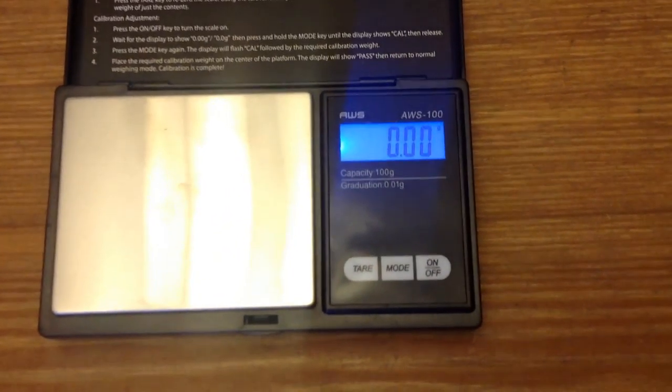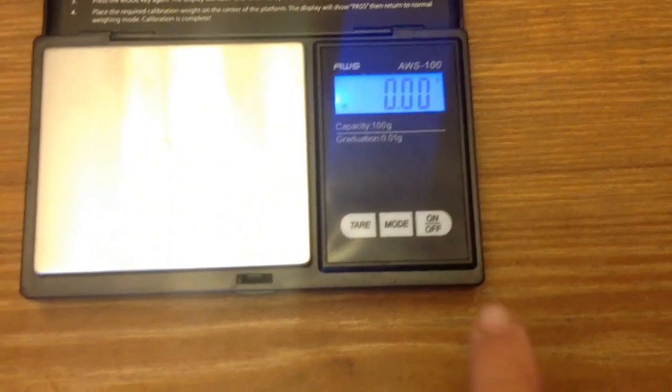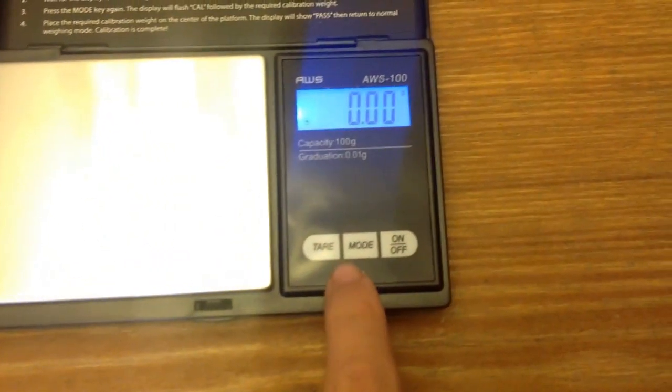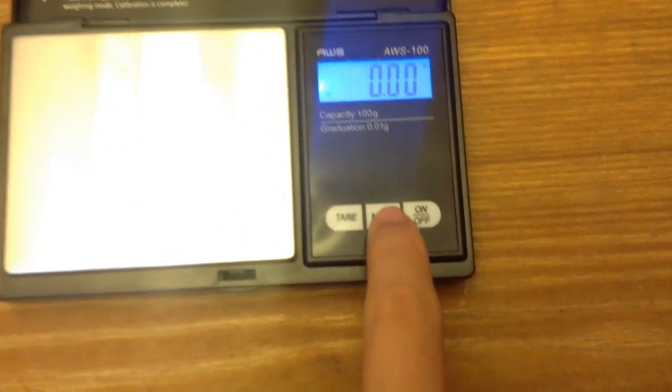I'm actually going to show you while we're here how to calibrate it. So if it comes off, you have a calibration weight and it says it's off, what you're going to do is hold down mode.